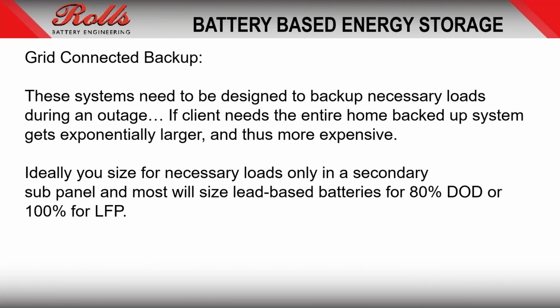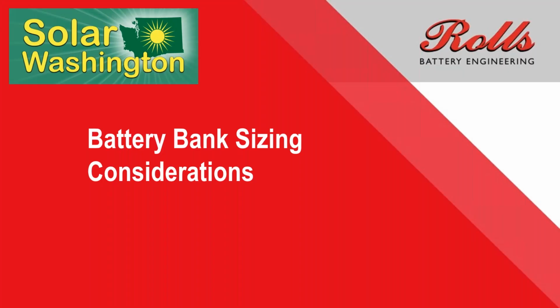Ideally, you size the necessary loads to the secondary sub panel. For lead acid batteries, 80% depth of discharge cycling, because it's going to be something that happens only 2, 3, 4, 5 times a year. If it's a lithium ferrophosphate battery, typically you size for that 80 to 100% depth of discharge. So we'll get into a little more of that on the calculations.